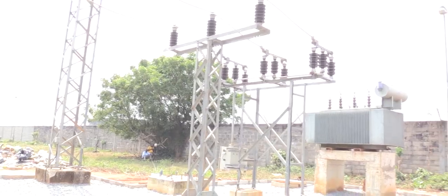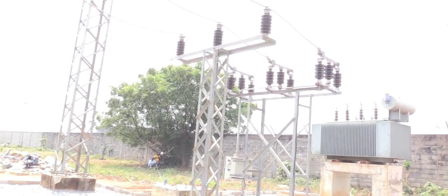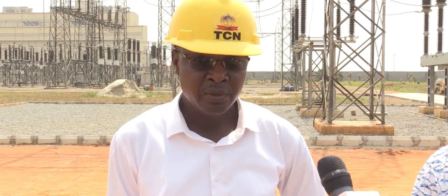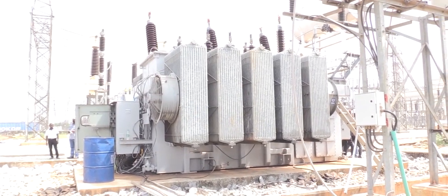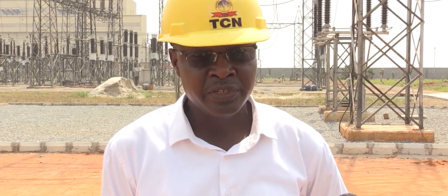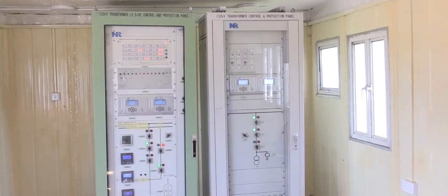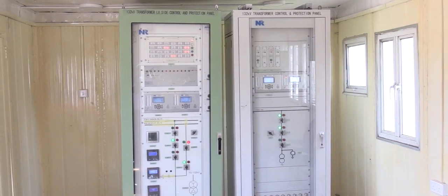The assistant transmission manager of Egbin substation, Engineer Moyo Oluwagbenga, described the substation's capacity: The substation itself has 6 outgoing and incoming 330 kV lines. By capacity, one of those lines can carry about 750 MVA, so you are talking in excess of 4,000 MVA. We also have 2 by 132 kV lines, each of which can carry 250 MVA, making 500. So the wheeling capacity of this substation you see here is in excess, close to 5,000.